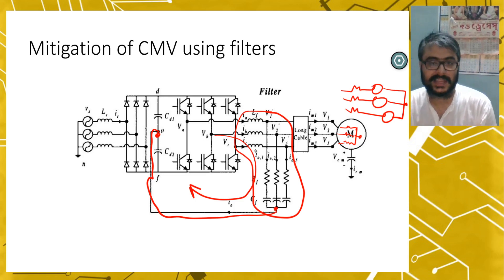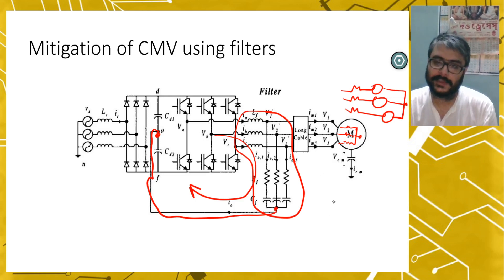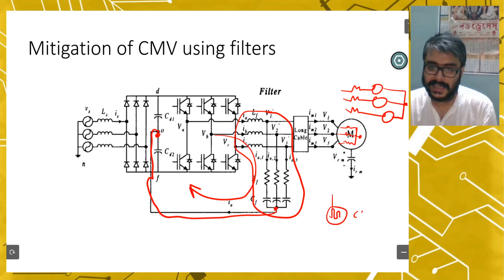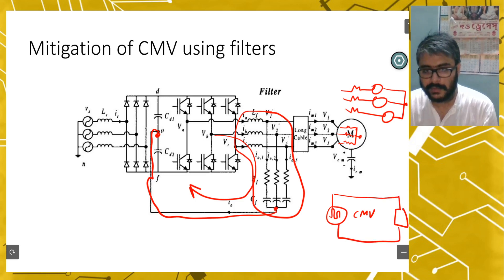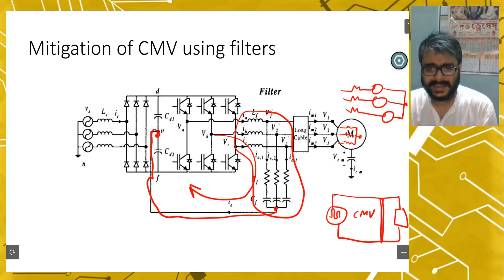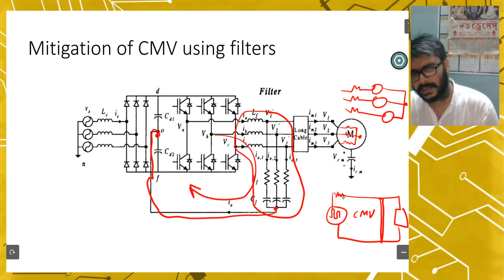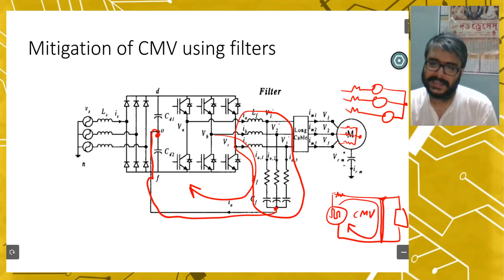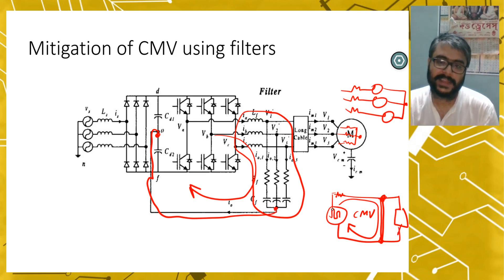So the common mode current or leakage current flows in the filter path and never flows via the motor. This common mode filter arrests this current and the motor is completely safe. The working principle is: if you have a CMV source with a load, and you short-circuit a low-impedance path, the common mode current will flow through the filter. The voltage across the load becomes zero because we have provided a very low impedance path for the CMV using the filter. This is how the load is protected.